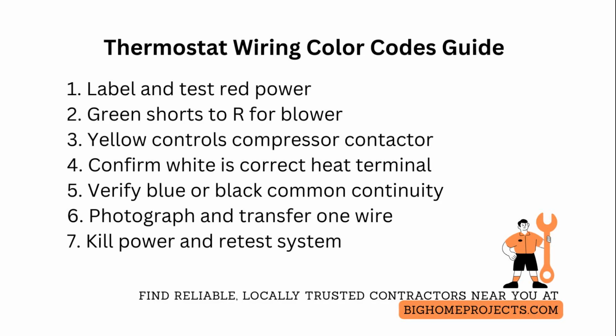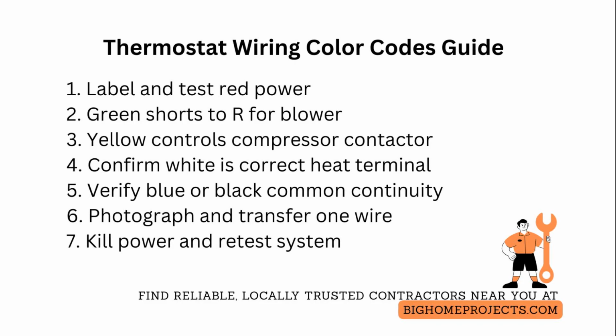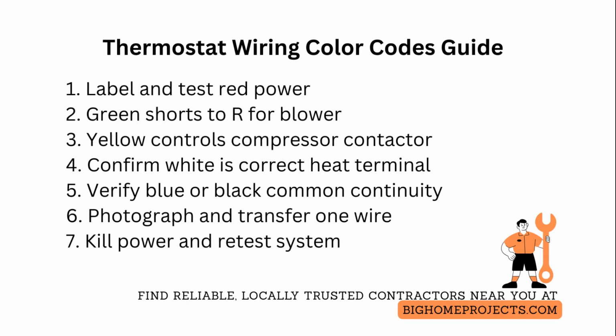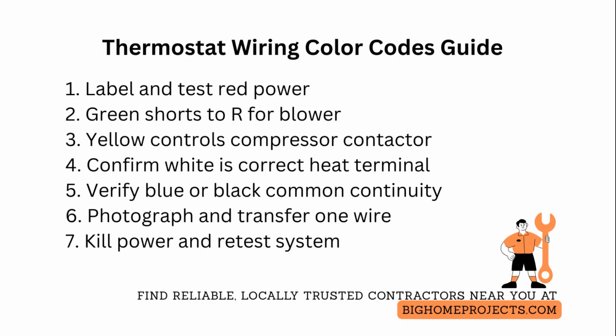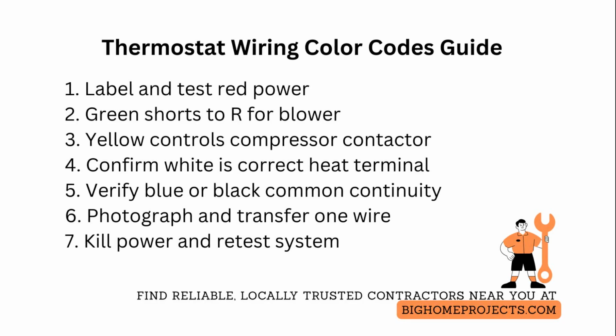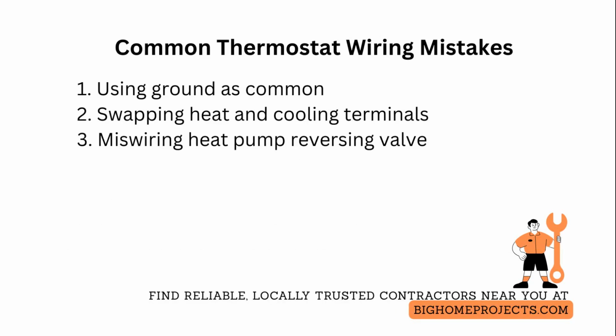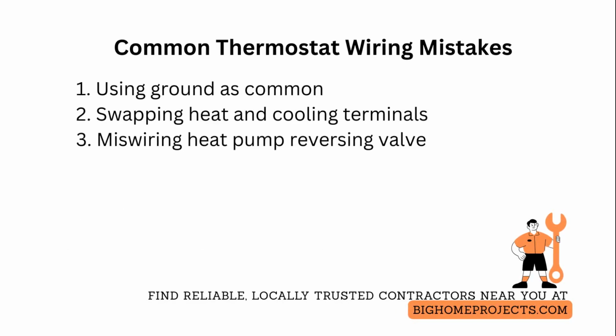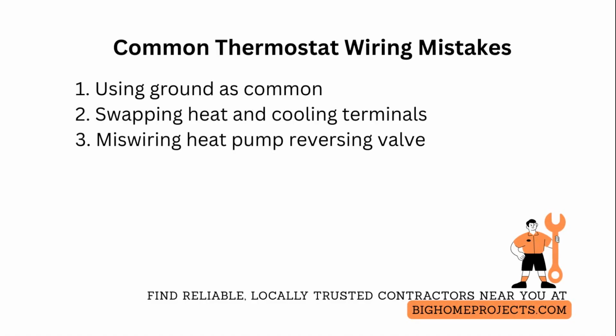Finally, always kill power at the HVAC breaker and retest the system after installation, checking that the furnace fan, heat call, and cooling call all respond correctly, and that there is steady 24-volt power between R and C before powering a smart thermostat. One of the most frequent thermostat wiring mistakes is misidentifying the common leg as a ground and wiring a thermostat to earth ground, causing intermittent power and device rebooting.